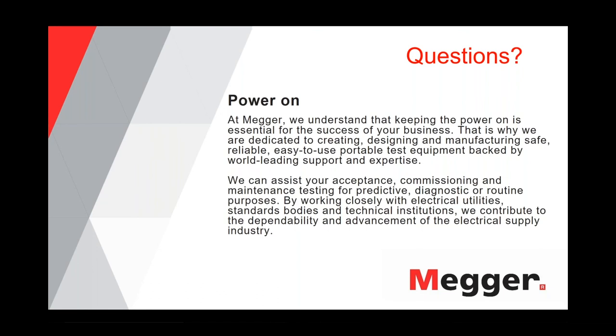Robert, what is the interval to conduct the VLF, TD, and PD testing for an aged cable? Okay, so there is no fixed interval for this. And as Henning pointed out, this has very much to do with where you are on the life curve, the bathtub curve, because a cable is an asset like a transformer or anything else. So you can say it has a life curve.